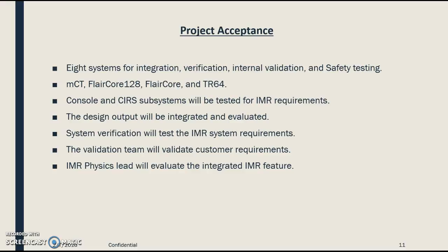The design output will be integrated and evaluated at the system level. The system verification lead will test the IMR system requirements on the Ingenuity and on the FLAIR and MCT scanners. The validation team will internally validate the IMR customer requirements. They will leverage the raw data from the previously externally validated project. In addition, the IMR physics lead will also evaluate the integrated IMR feature to ensure that technical specifications of IMR and the scanners are met.